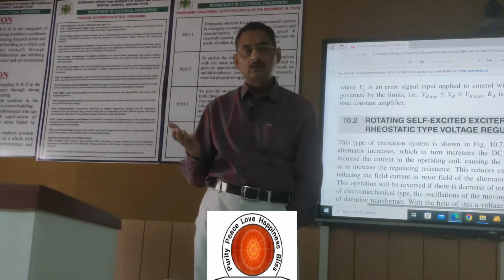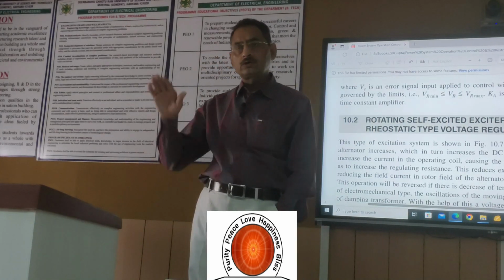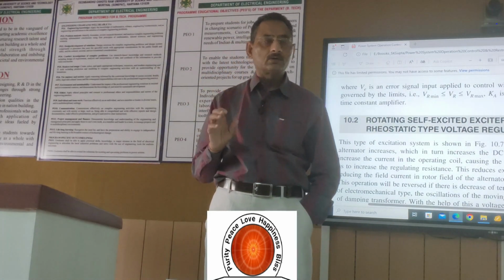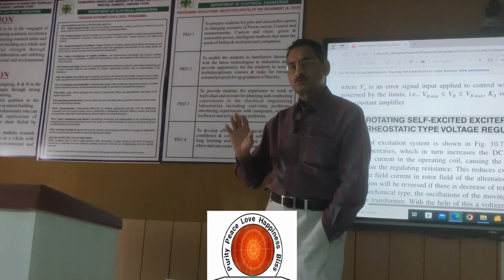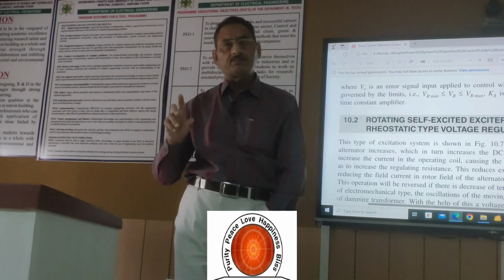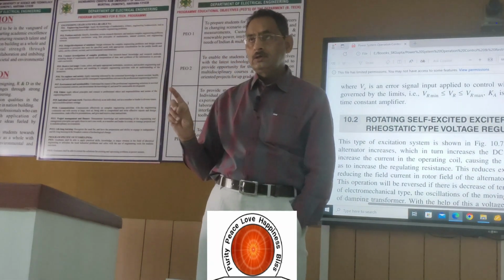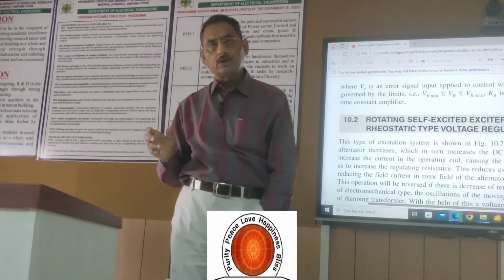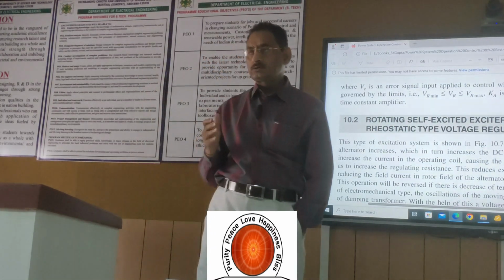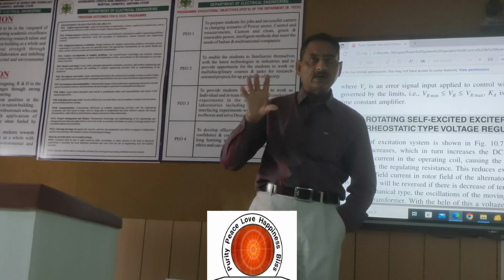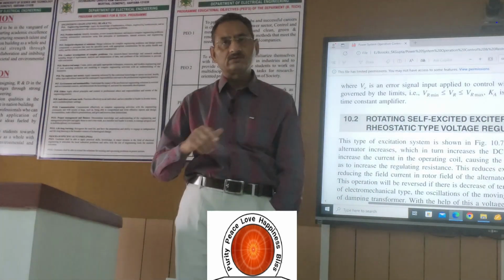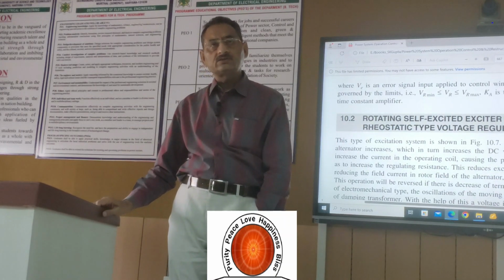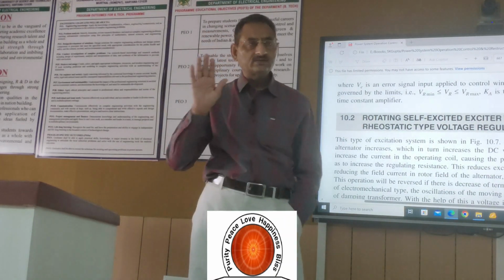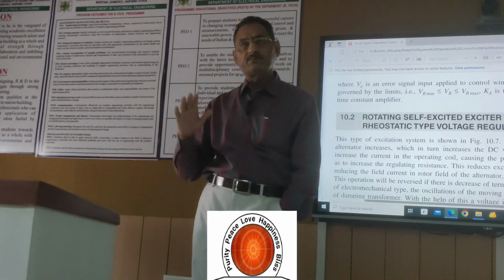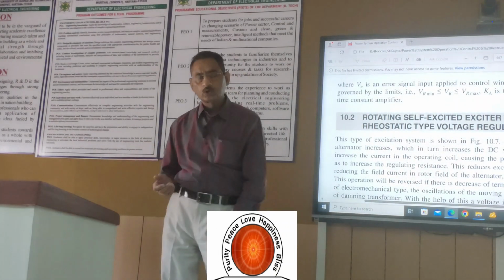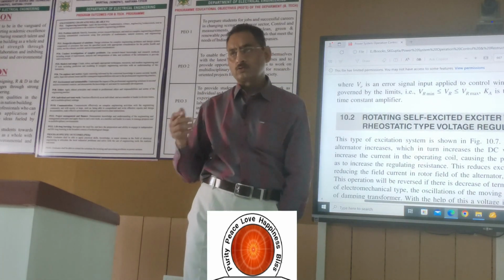Means voltage can be more than 1 per unit or it can be less than 1 per unit depending upon the reactive power. So it is our responsibility as power engineers to supply the reactive power as per the demand. And demand is continuously changing, so we have to continuously monitor and continuously change the reactive power supplied. And this is done through the excitation system. Excitation system, as I told, is the sum of exciter plus control system. Exciter plus its control is called the excitation system. Sometimes it is also called a voltage regulator.